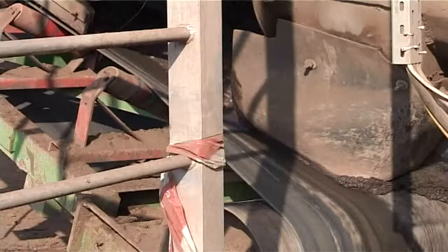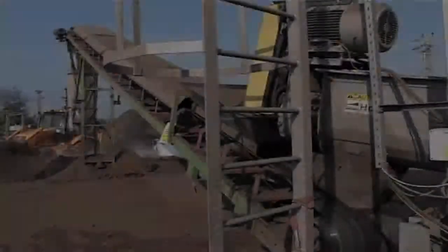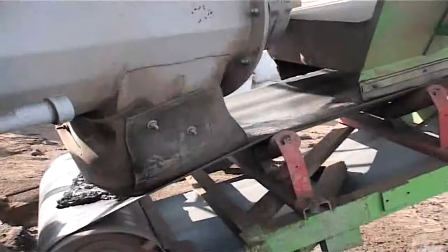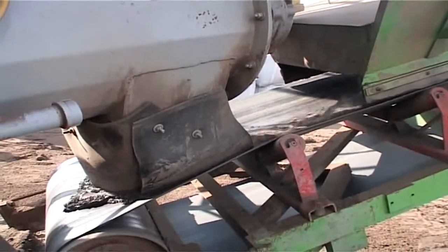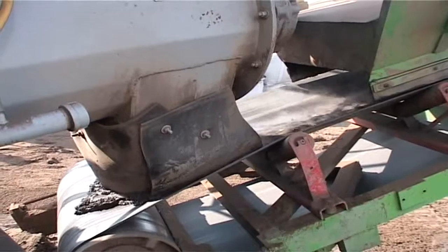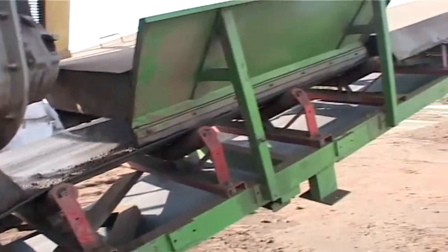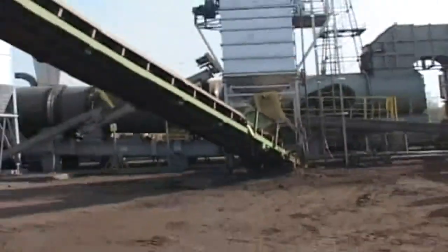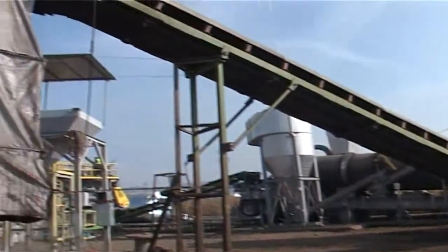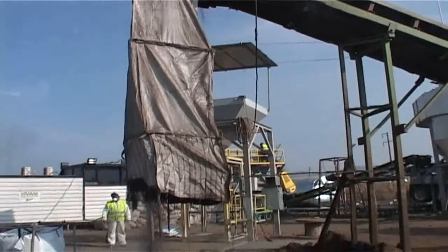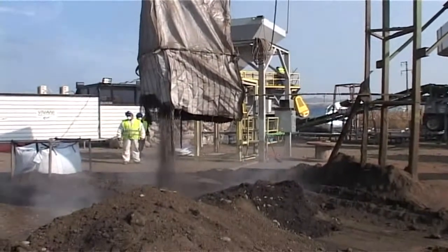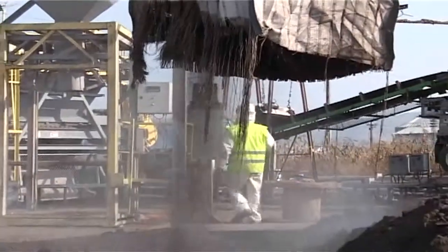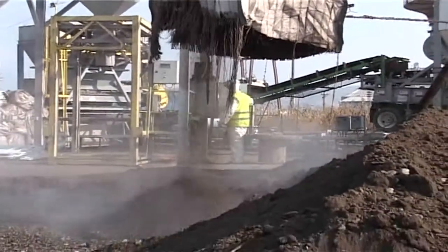The sludge stored on the temporary platform has the following features: humidity higher than 15%, content of TPH, total petroleum hydrocarbon, higher than 5%. From the temporary platform, the sludge is loaded in the storage tank of the centrifugal. The sludge is carried by a conveyor worm from the feed bin into the centrifugal. Once there, the sludge is subject to the centrifugal action, which involves dehydration and removal of total petroleum hydrocarbons.